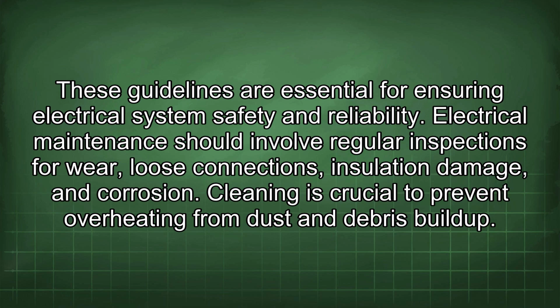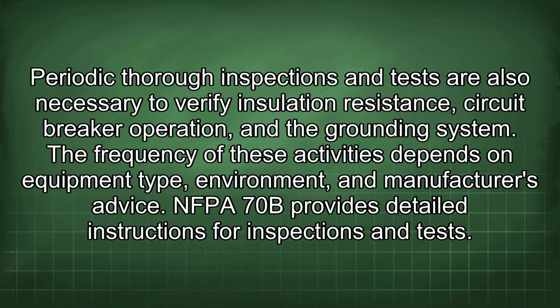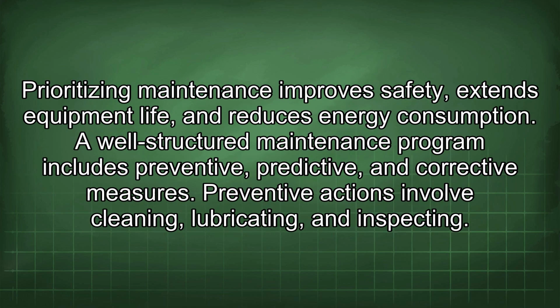Electrical maintenance should involve regular inspections for wear, loose connections, insulation damage, and corrosion. Cleaning is crucial to prevent overheating from dust and debris buildup. Periodic thorough inspections and tests are also necessary to verify insulation resistance, circuit breaker operation, and the grounding system. The frequency of these activities depends on equipment type, environment, and manufacturer's advice. NFPA 70B provides detailed instructions for inspections and tests. Prioritizing maintenance improves safety, extends equipment life, and reduces energy consumption.